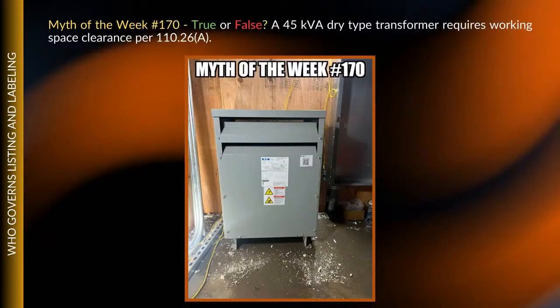Now, if I look at 110.26, it says working space, then you're going to go down and pick up A - and right there, what is that heading? Working space. So it says you need working space for equipment that is likely to require examination, adjustment, service, or maintenance while it's energized. That's it. So I agree, all electrical equipment has to have working space, but the only time it needs that working space is when you're going to follow the working space requirements that are in 110.26. And when you pick it up, that'll be A1 through A4.